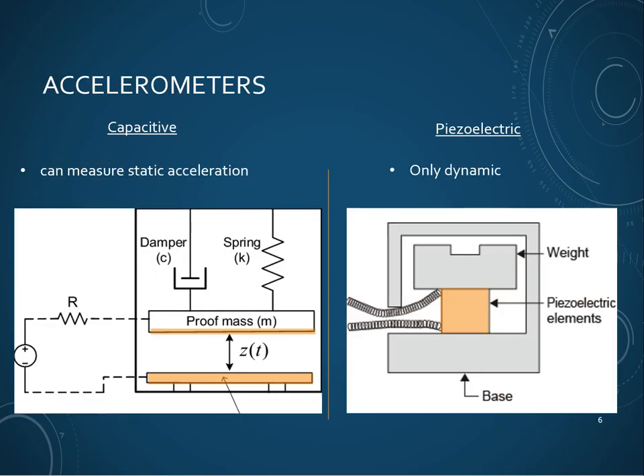Starting with accelerometers: there are generally two types we deal with — capacitive and piezoelectric. Capacitive accelerometers work on the basis of capacitance, which is the ability of a material to hold electrical charge for a given voltage. These accelerometers generally have some kind of a proof mass with two surfaces that have capacitance properties. Between these two surfaces there is generally a ceramic through which DC electricity cannot flow — this material is called a dielectric.